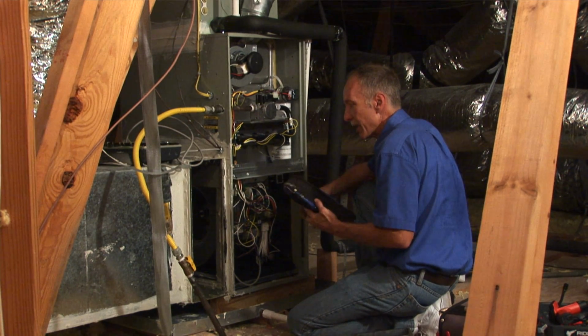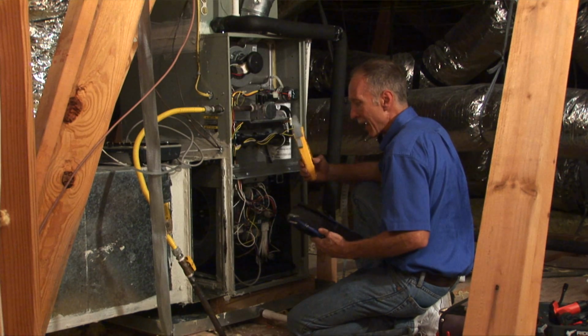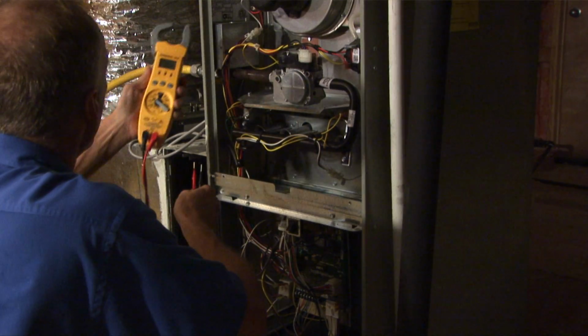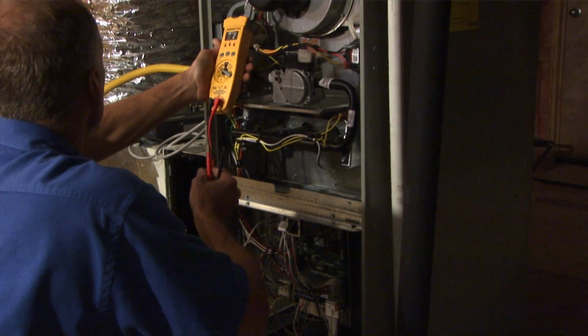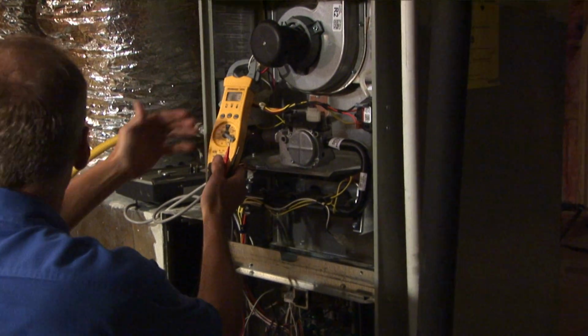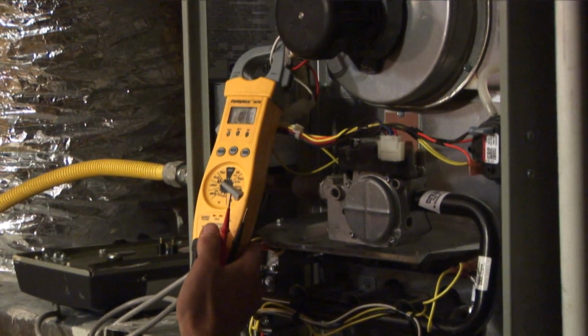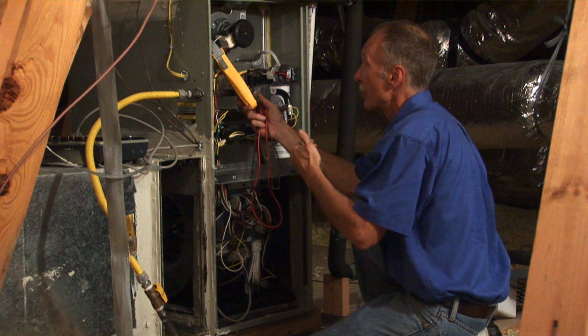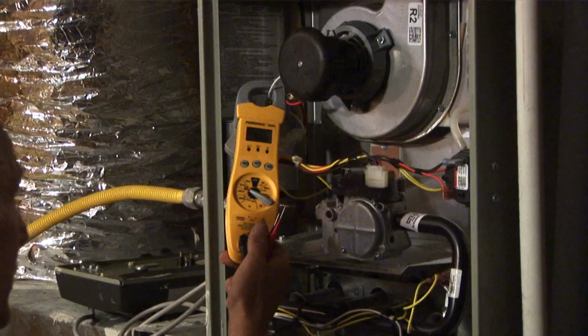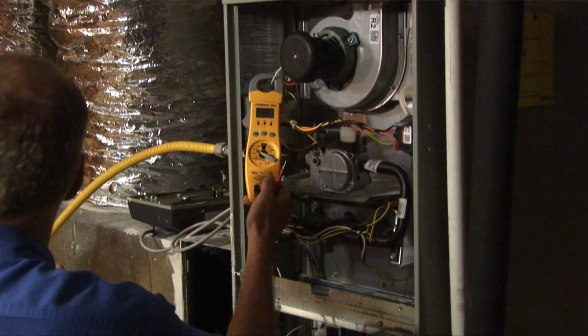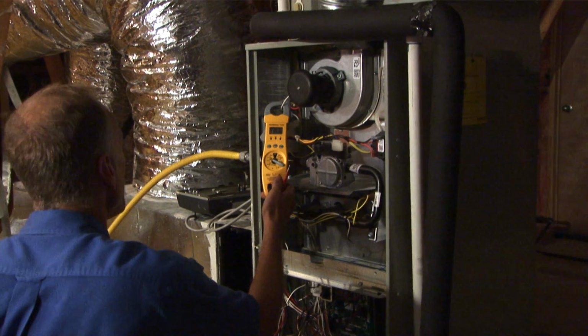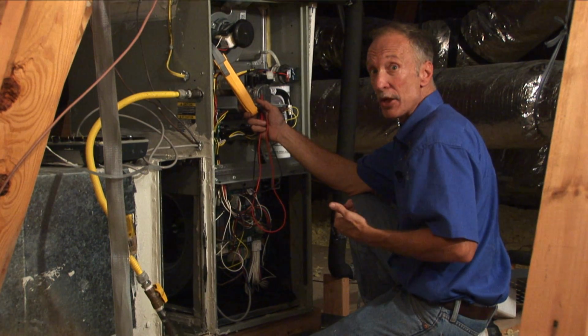We do this using a digital amp voltmeter. Right now I'm clamping this on the induced draft motor. I'm using the clamp-on portion of this meter, and this is going to tell me whether or not I'm getting a correct amp draw. This is important because if I'm not getting a correct amp draw, then it's a sign of possible failure.